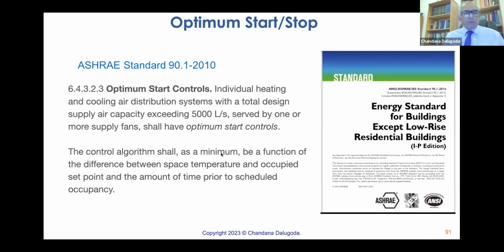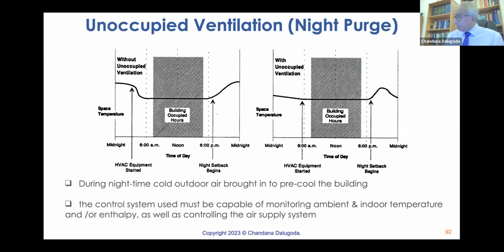So optimum start is in the ASHRAE standard, and is required for 5,000 liters per second air supply and above. We'll have to use it. Then the night purge. For night purge, you'll have to have the AHU and pre-design that. What it does is use outdoor air when the outdoor air temperature is below 24 degrees to cool the building during the night. At a predetermined time, both exhaust and fresh air dampers open. Only the fresh air system operates to cool the building. Fresh air comes in and circulates through the supply ductwork. Return air does not recirculate, it will be extracted.